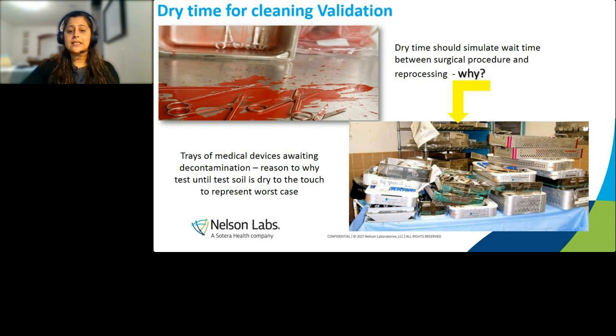Once it's bone dry, that's when we will start the cleaning validation. So we're challenging the processing. The reasoning for that is, if you see this picture here, we got this from one of our customers that was working with us. They told us that devices sit in these trays, right? Soil can seep down, and you have to get these cleaned in an 8-hour period, but they can be dried before they get to them. So that's why you want to challenge the process, so that if the device is dried, the cleaning instructions outlined in the IFU can still be feasible and will get the device cleaned. So we do challenge it until the test soil is dry.